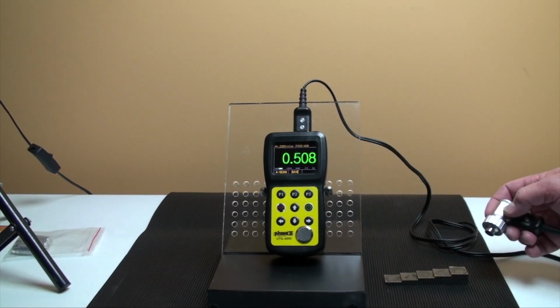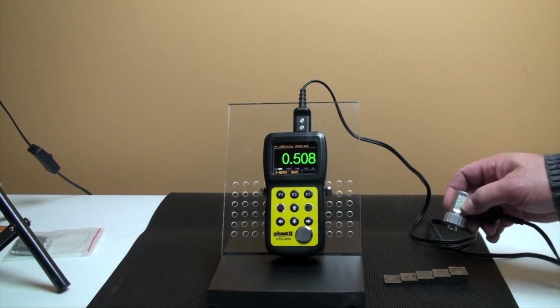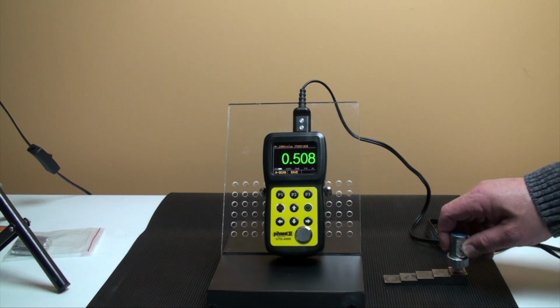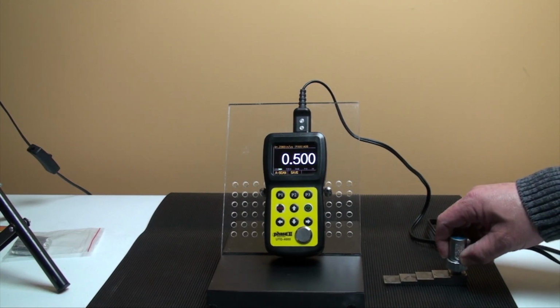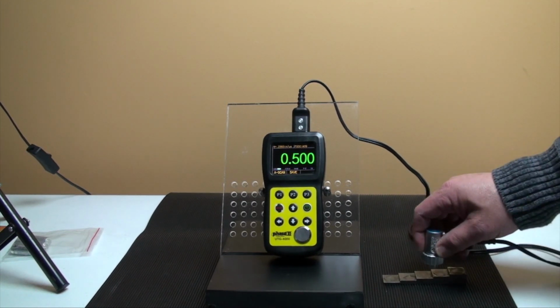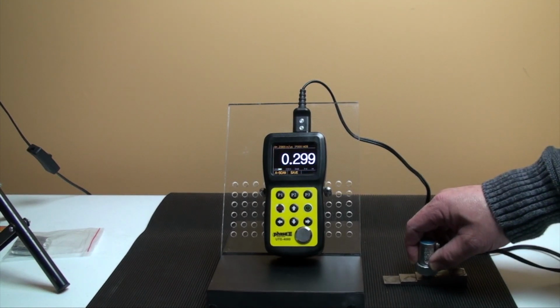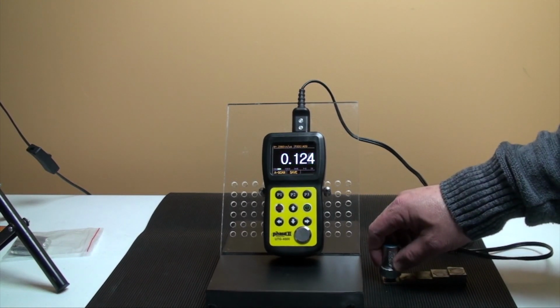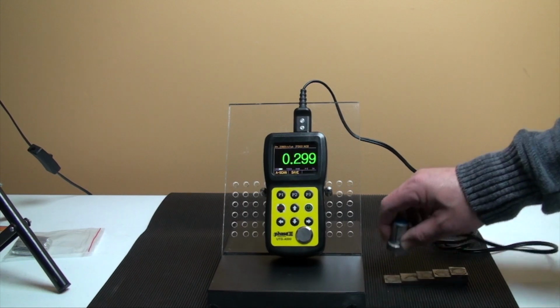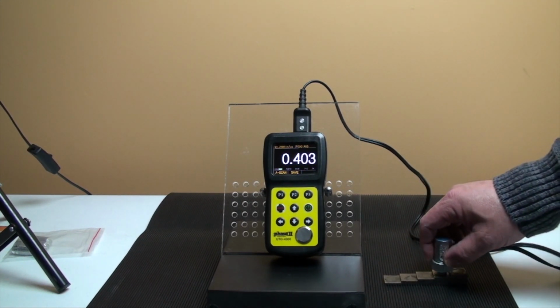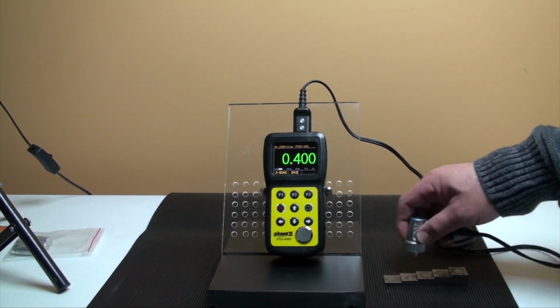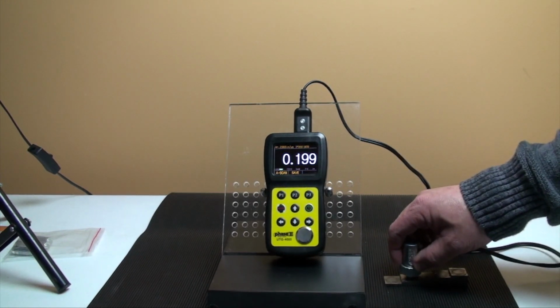Taking tests is very easy. After making sure your measuring parameters are set correctly, inch and metric and velocity of the material, place a small amount of gel on your workpiece and then follow with the probe on the workpiece. Readings will show on the screen. Be certain not to use too much gel. Use just enough to remove air from between the probe and the test material.